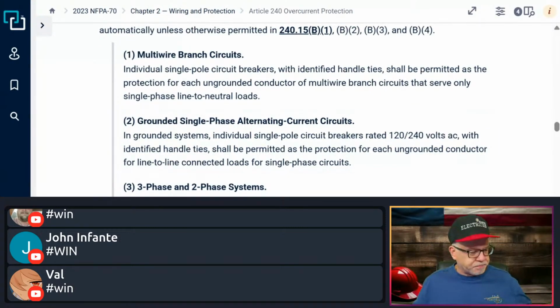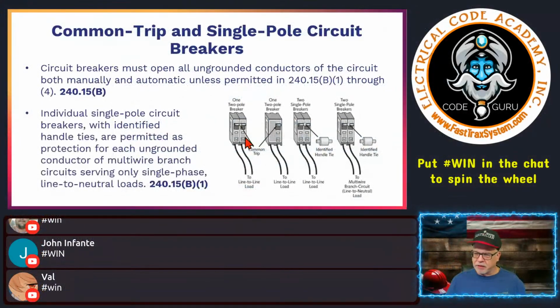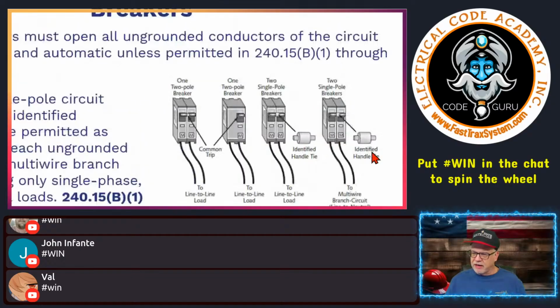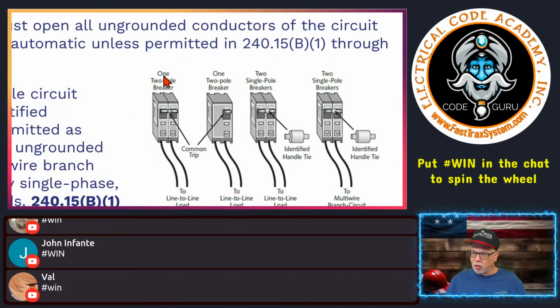Easiest thing, I guess, for us is to look at this example picture, and I'll try to blow this up a little bit. So we have right here a two-pole breaker. One two-pole breaker, common trip. They look familiar. Some of the brands can have just one breaker switch on it, and then some could look like they're two separate breakers, but they're actually molded together. This is line-to-line applications, and this is line-to-line applications. Here's the application where you have two single pole breakers. Again, side by side is okay as well if it has an identified handle tie for line-to-line loads.